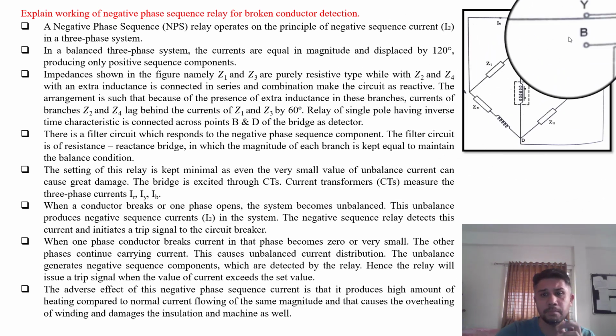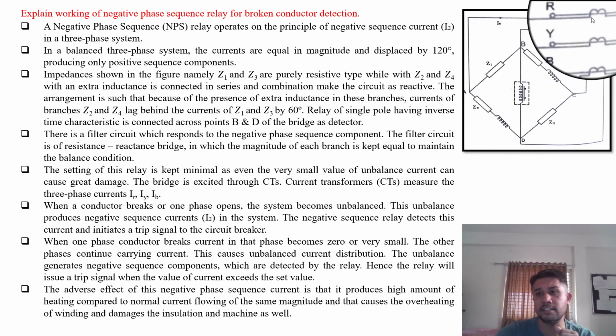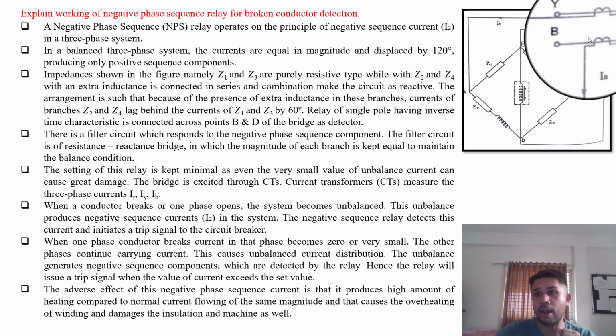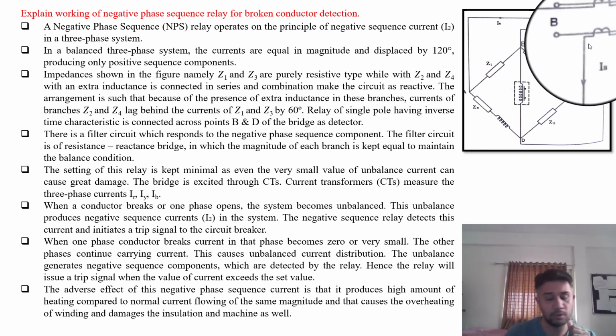Current transformers measure the three-phase currents, that is IR, IY and IB respectively. Now when a conductor breaks or one of the phases opens up, the system becomes unbalanced. This unbalance produces the negative sequence current I2 in the system. The negative sequence relay detects this current and initiates a trip signal to the circuit breaker.